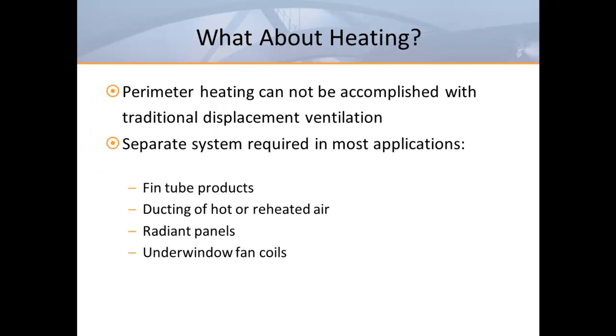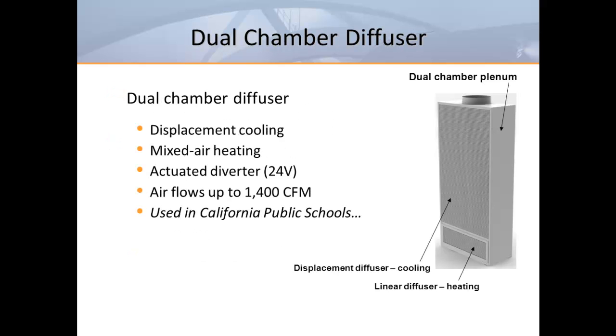Displacement ventilation is only suitable for cooling, but there is an interesting way to deal with heating requirements. Traditionally, displacement ventilation has required the use of separate perimeter heat to deal with loads from exterior walls and perimeter glass — often meaning fin tube products, separate ducting of hot air, radiant panels, or under-window fan coil units. Here's an interesting solution: a relatively new product design called a dual-chamber displacement diffuser.